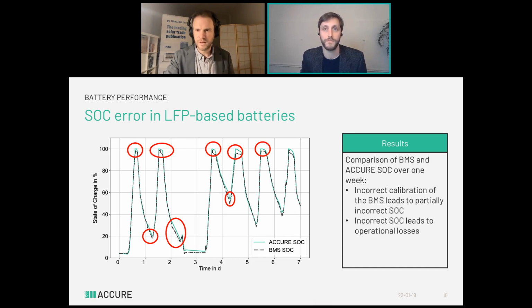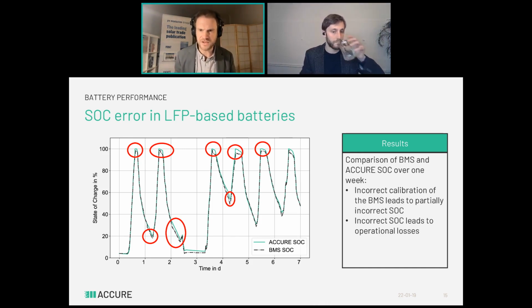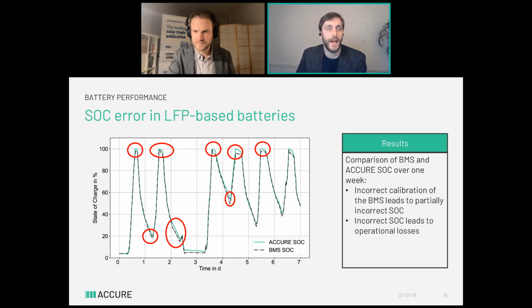Another SOC question: the average SOC estimation difference we see here is in the range of 3%. Is that critical for aging estimation as well as safety over battery lifetime? I'd say 3 to 5% is not critical for aging or safety. The thing we see with LFP that could be safety critical is if you're too optimistic on the state of charge, you might run into a deep discharge, because the local SOC estimation tells you there's still 5% energy left, and when you try to tap into that you find there was nothing left, and you're already below what's technically specified. Tesla has run into this problem with their China LFP cars a lot, and we've seen other companies run into it too.